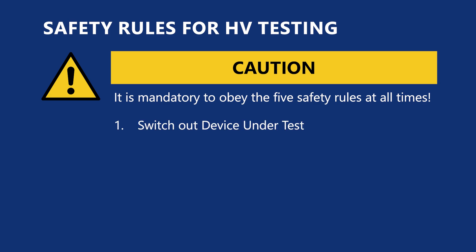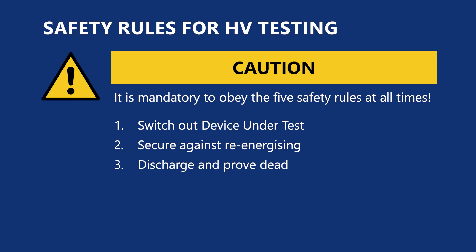Switch off the device on test, secure against re-energizing, discharge and prove dead, ground and short circuit, and cover and close off nearby live parts.